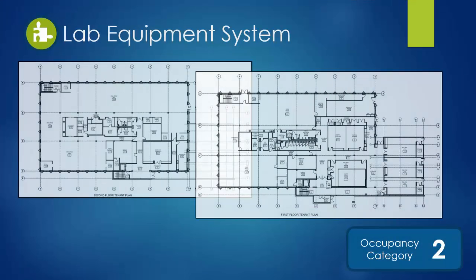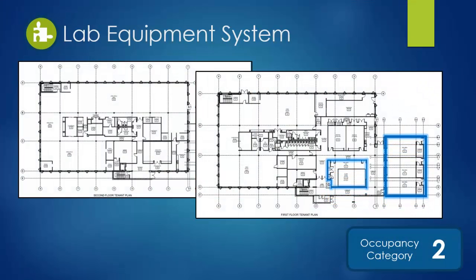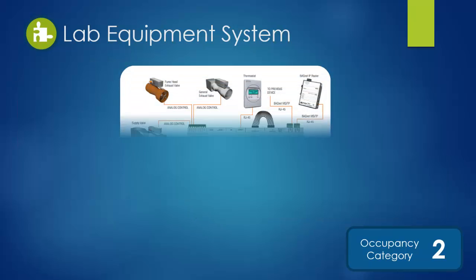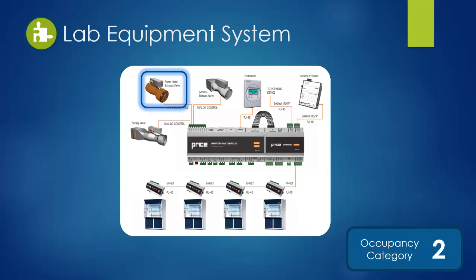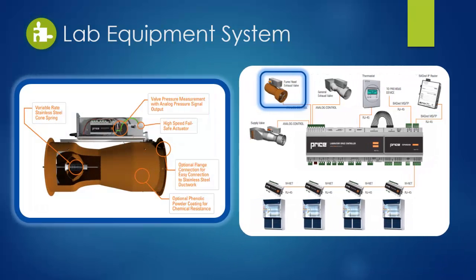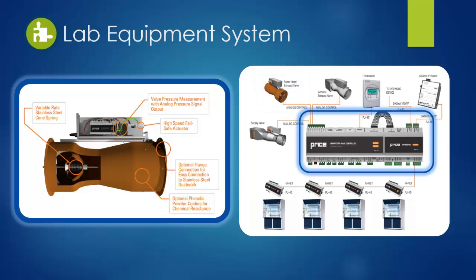A special lab equipment system will be used in the research and development areas to make up occupancy category 2. The owner's requirements for lab equipment within this space resulted in a high quantity of exhaust. Therefore, a sophisticated system is needed to regulate the varying exhaust. Venturi valves will be used to effectively regulate room supply, room exhaust, and hood exhaust rates. A laboratory controller will connect the Venturi valves with a thermostat, room pressure sensor, and fume hood controllers to maintain the required room pressure and exhaust.